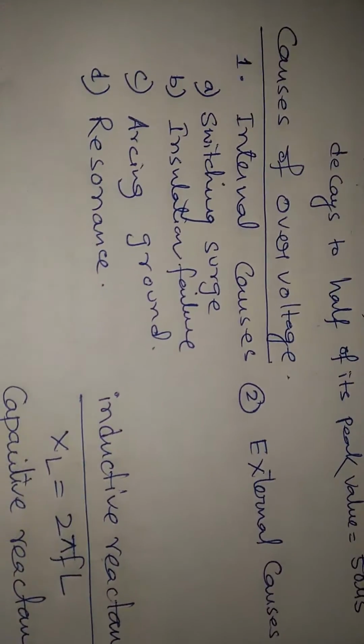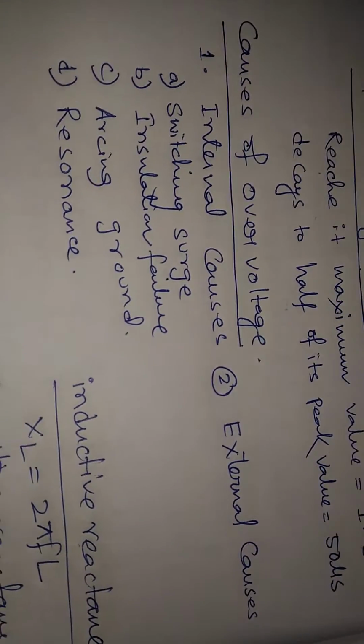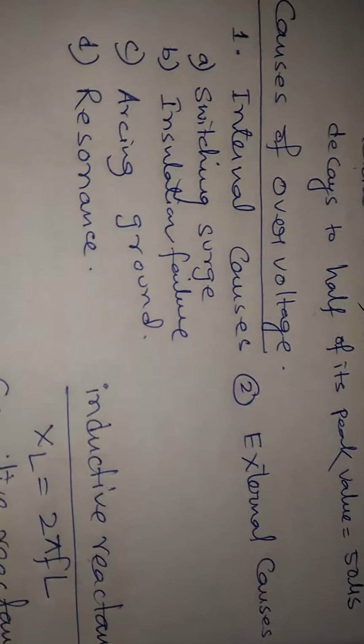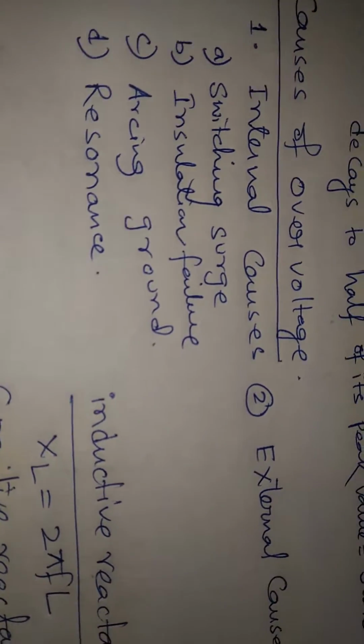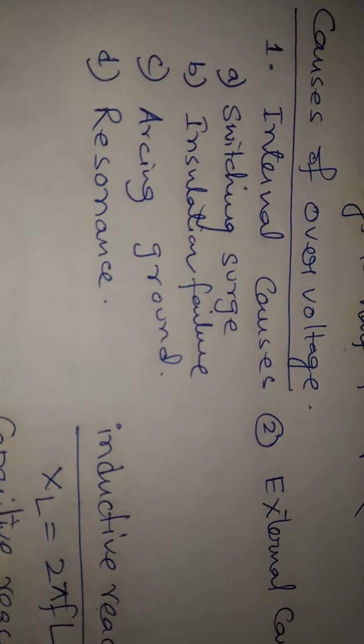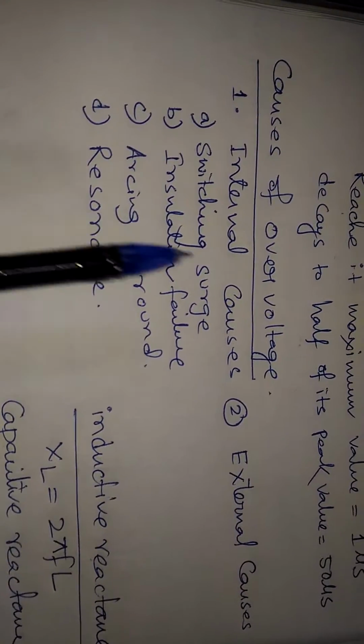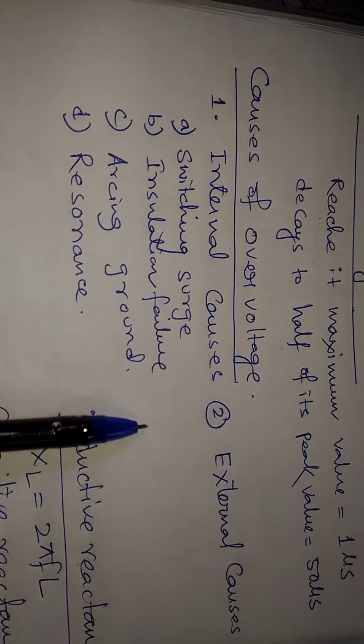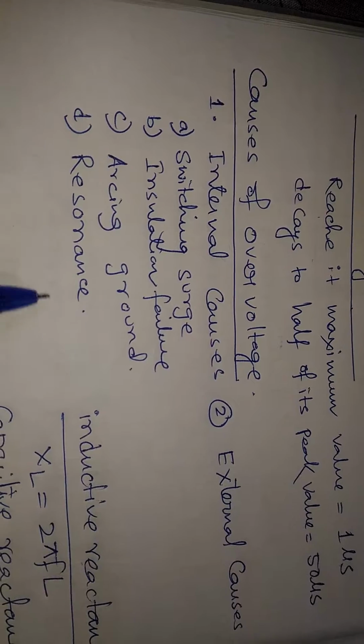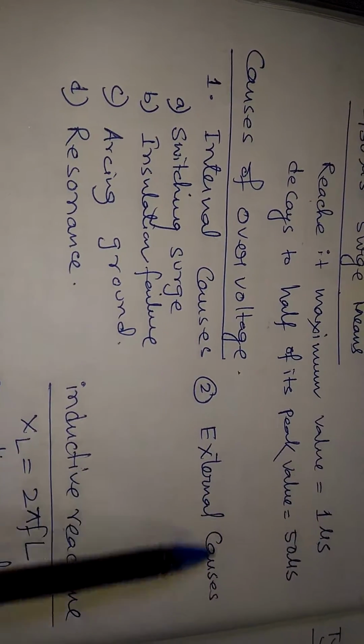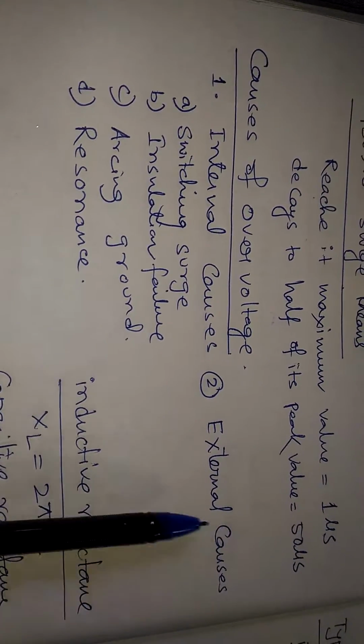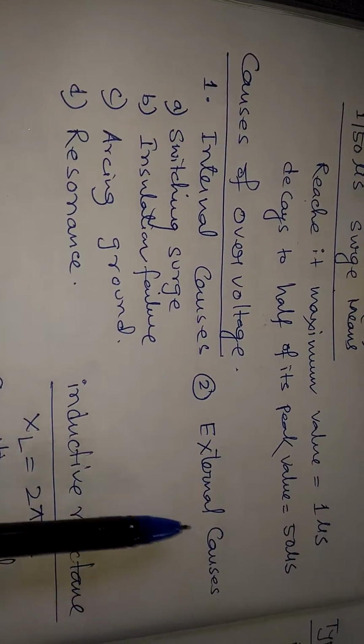And what is the cause of voltage surge? The voltage surge may be caused by internal causes or external causes. What are the internal causes? Internal causes are switching, insulation failure, arcing ground, and resonance. And what are the external causes? The external cause is only lightning.